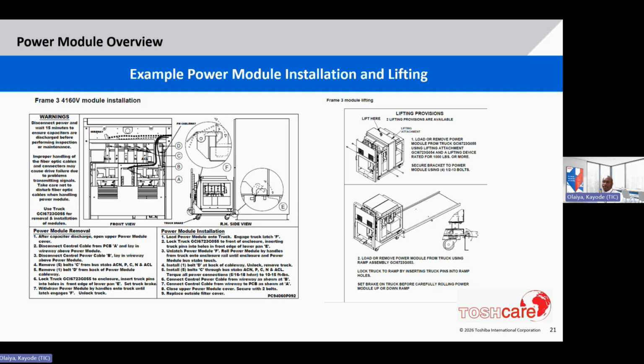For this particular example, which is a frame 3 4160, the module can be racked out onto the truck assembly I mentioned, which we sell. And then there is a ramp that can be attached to that truck assembly for rolling the module onto the floor. And the lifting bracket attached to the module can be used to lift it to and from wherever it needs to go. And as I mentioned, this label is on the drive for those who have questions about it.